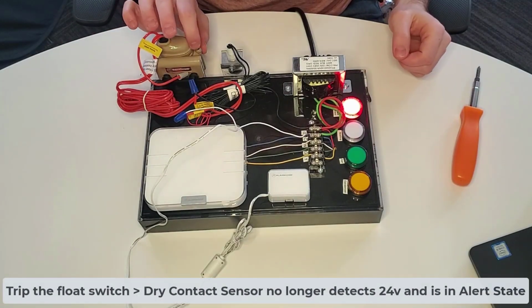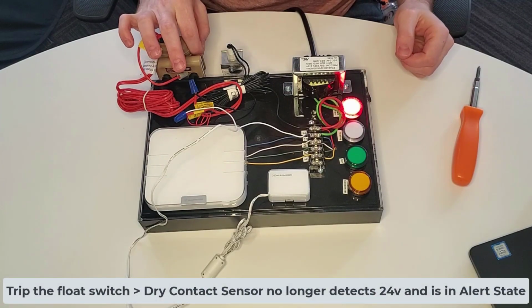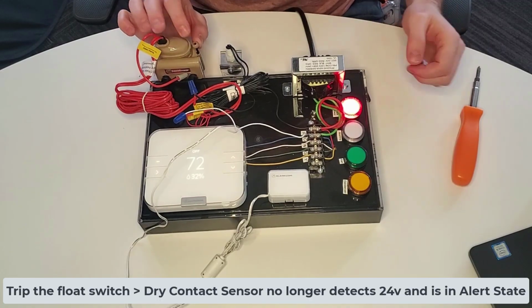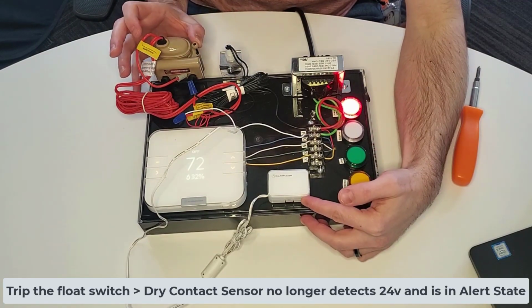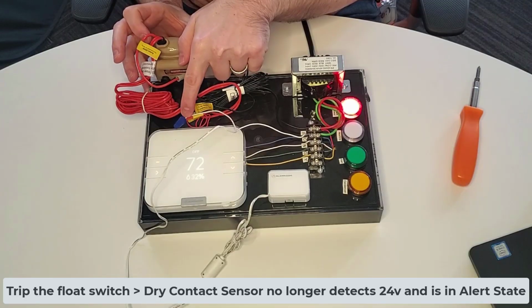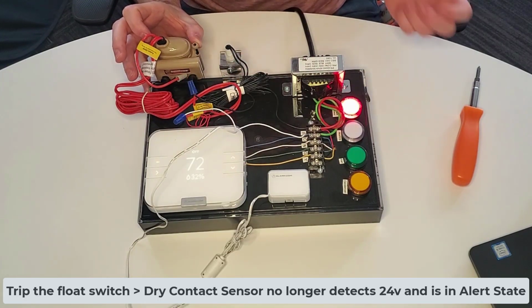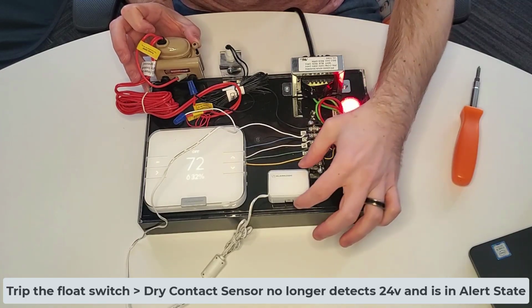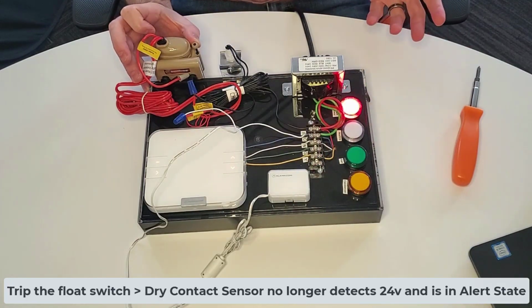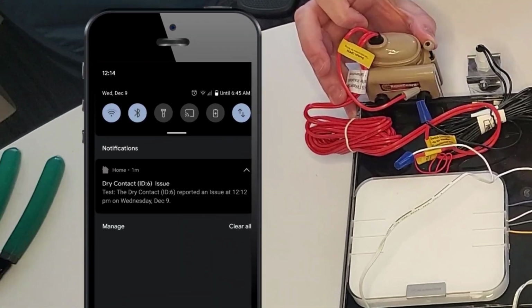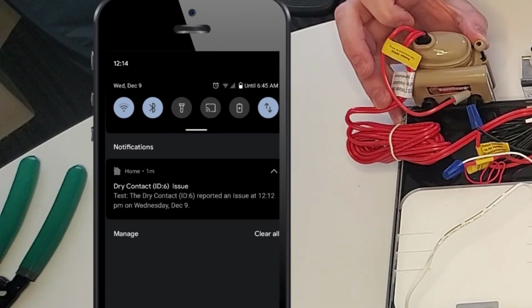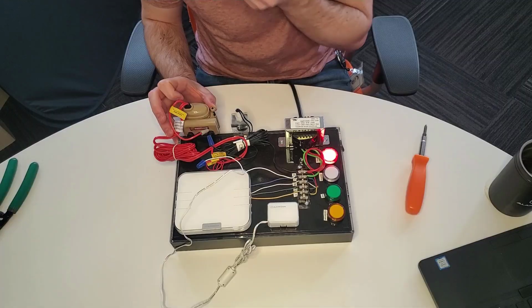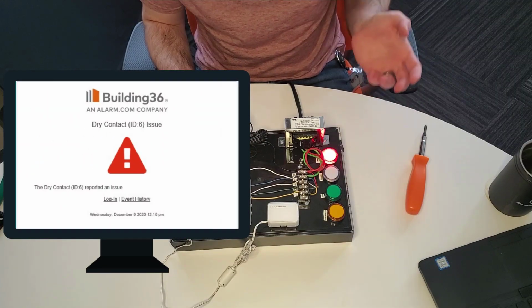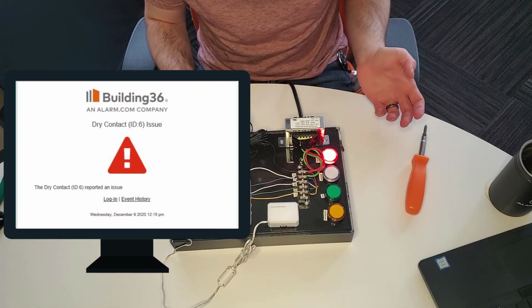When we trip the float switch for a test, the dry contact sensor no longer detects the 24 volts between the float switch and common, and the light blinked, and at this point in time the customer would receive a notification that the dry contact sensor is in an alert state, and on the partner portal it would be considered a customer trouble condition.